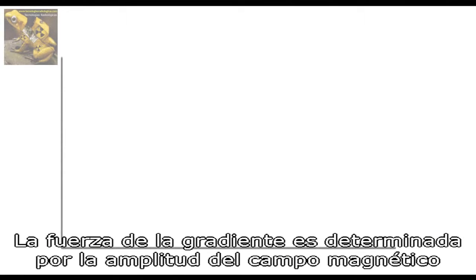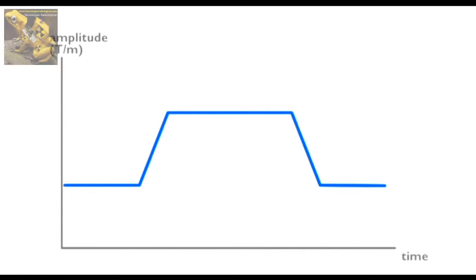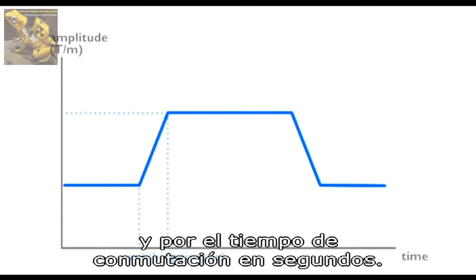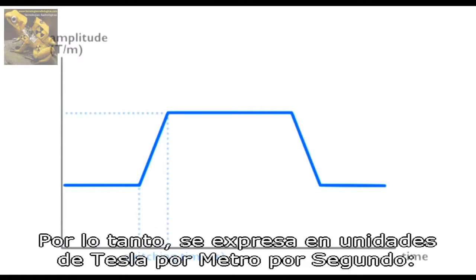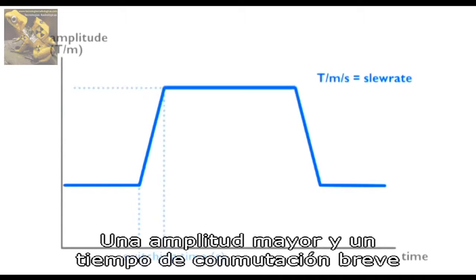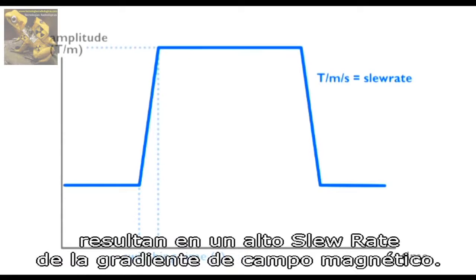The strength of the gradients is determined by the amplitude of the gradient magnetic field, measured in Tesla per meter, and by the switching time in seconds. It is therefore expressed in units of Tesla per meter per second — the slew rate of the gradient system. Higher amplitudes and shorter switching times result in a higher slew rate of the gradient magnetic field.